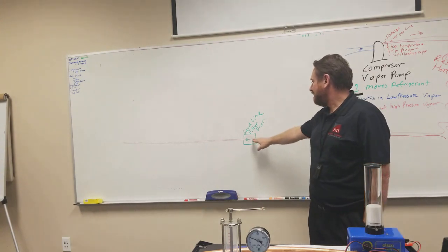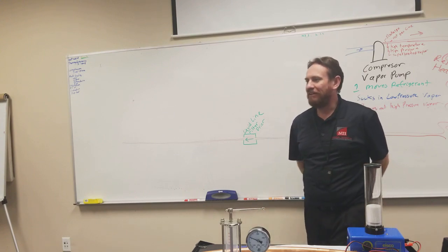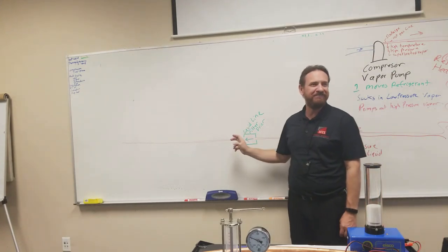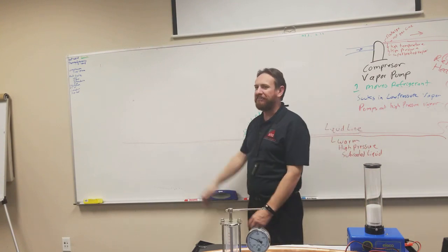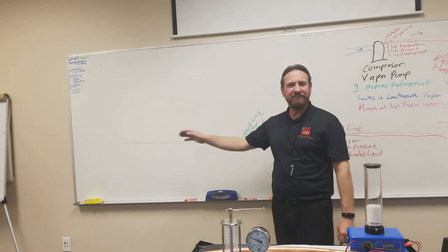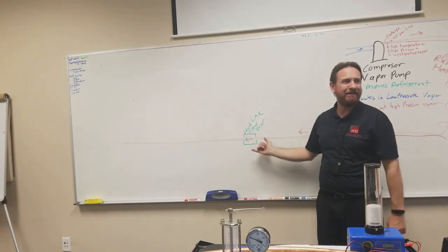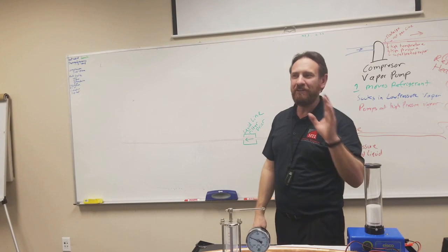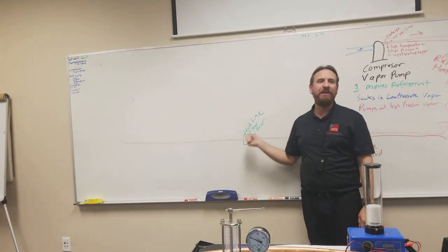These will last for 30 or 40 years. They'll last a long time. But once you open the system for any reason, say I installed it, turned the system on for 2 minutes, and shut it off, got to fix a leak, do something else, I have to take the refrigerant out, cut this guy back out, and put a brand new one in. So if you never open the system, you don't have to change it. But if you open the system, then you must change that filter dryer.